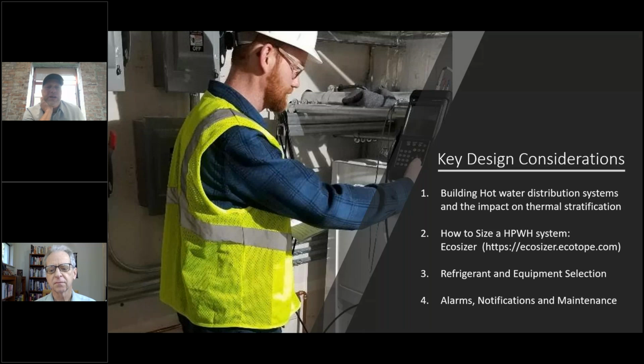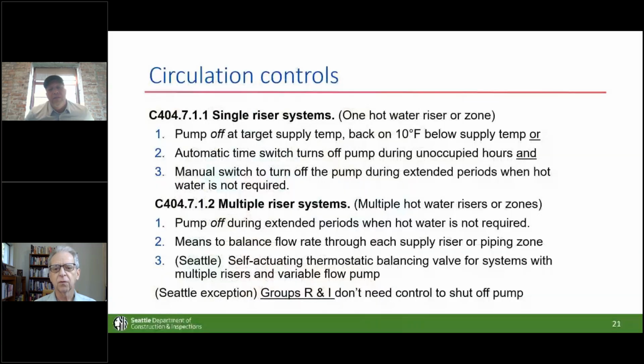One thing, maybe backing up there, Duane, is that Group R is exempt. I've seen some other projects where we've tried to turn the circ pumps off on Group R, and I don't recommend it. So that's really an important exception there. Some people need to take a shower at 2 a.m. So Group R and Group I, so that would be hospitals and nursing homes and correctional facilities and the like.